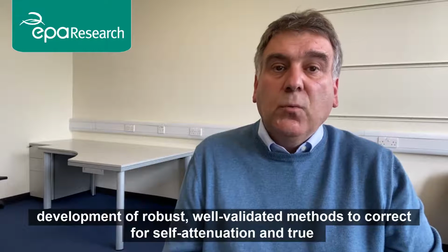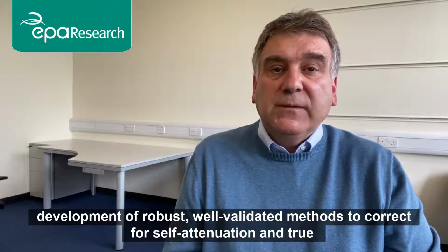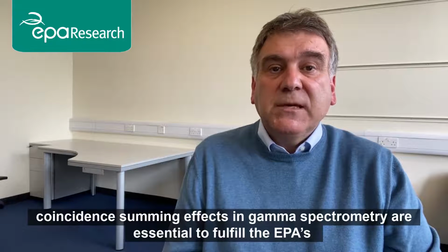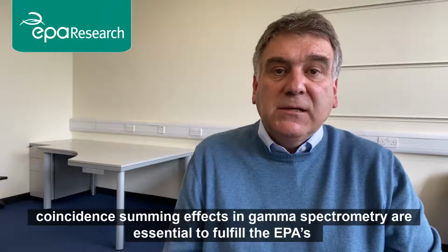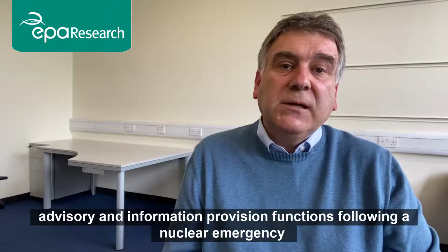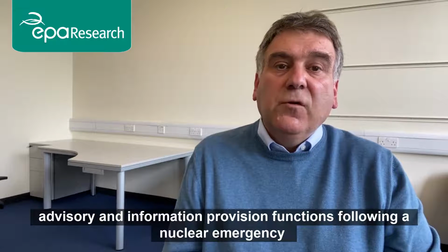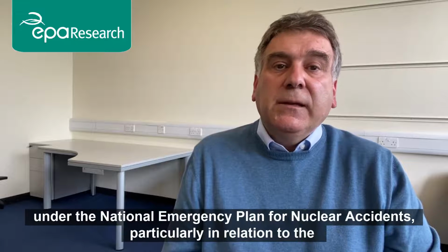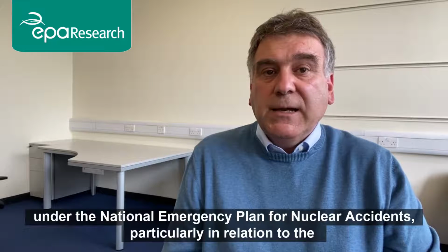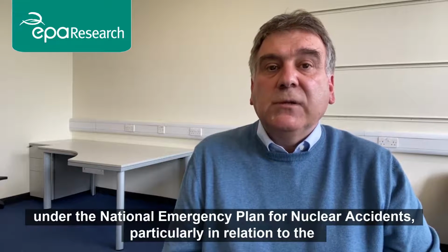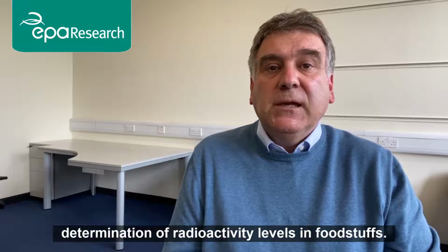The accurate calibration of the gamma detectors in use at the EPA's radiometric laboratory, and the development of robust, well-validated methods to correct for self-attenuation and true coincidence summing effects in gamma spectrometry, are essential to fulfill the EPA's advisory and information provision functions following a nuclear emergency under the National Emergency Plan for Nuclear Accidents, particularly in relation to the determination of radioactivity levels in foodstuffs.